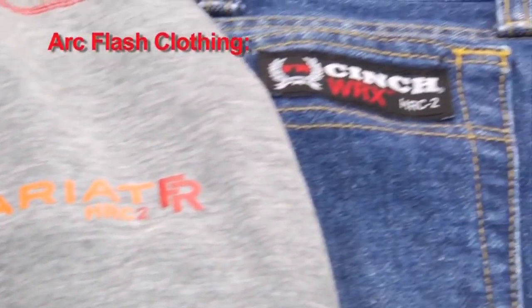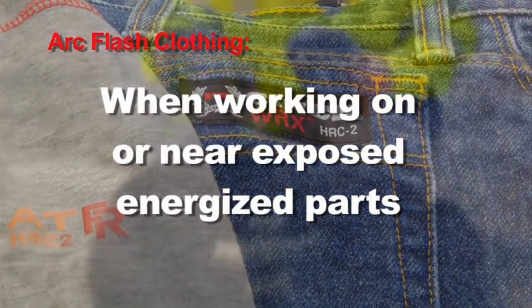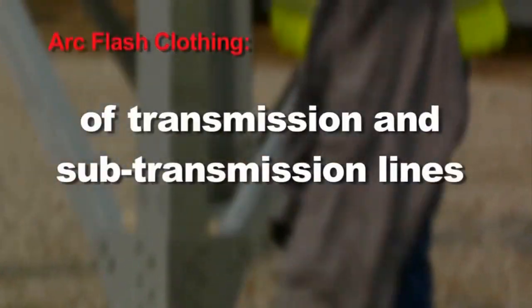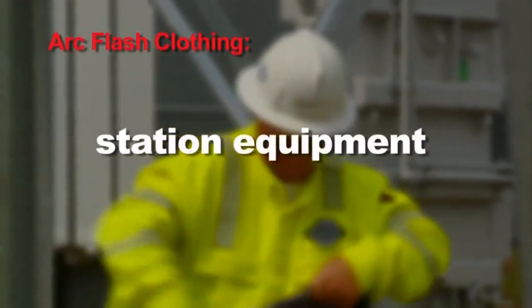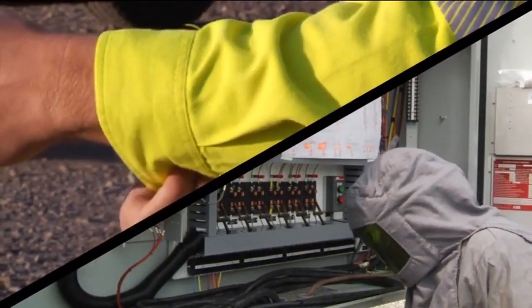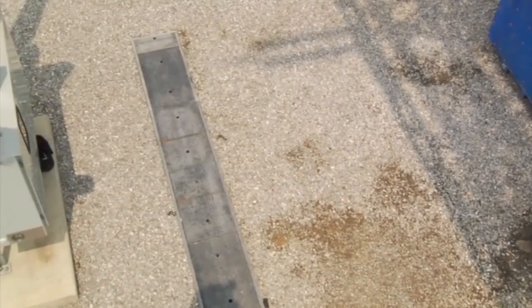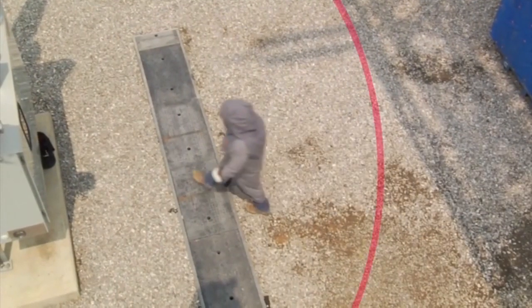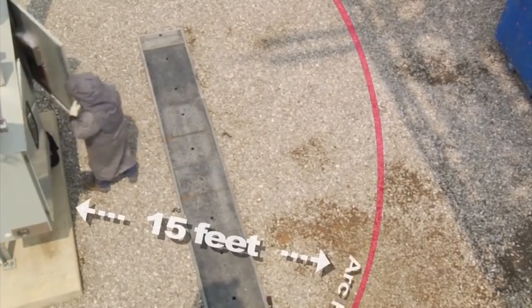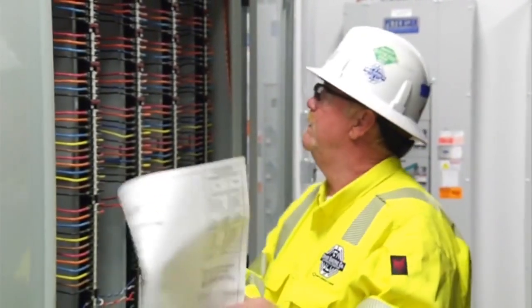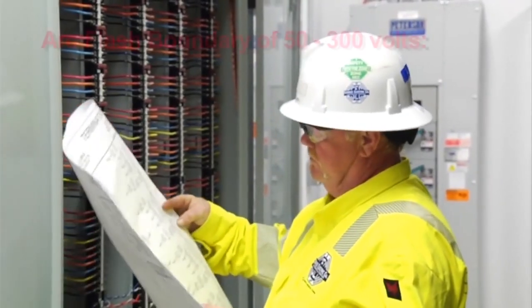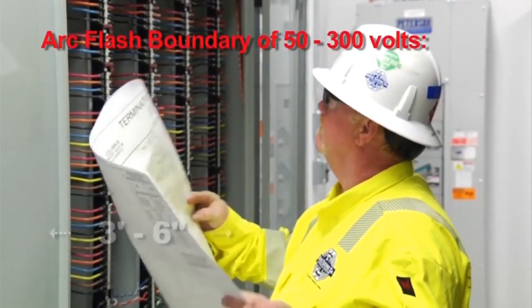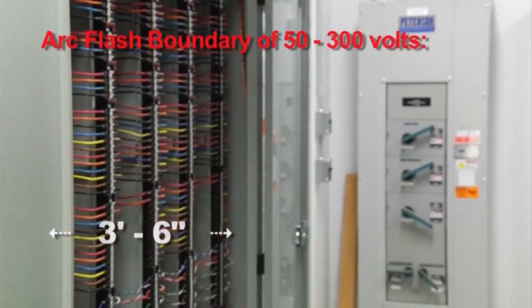Arc flash rated clothing is required for qualified electrical workers while working on or near exposed energized parts of transmission and sub-transmission lines and any station equipment. This clothing must be in compliance with AEP, local, state, and federal guidelines. When in a substation, unless identified differently, the arc flash boundary to exposed energized parts is 15 feet. Unless identified differently, the arc flash boundary to exposed energized parts of 50 to less than 300 volts in a control house is 3 feet 6 inches.